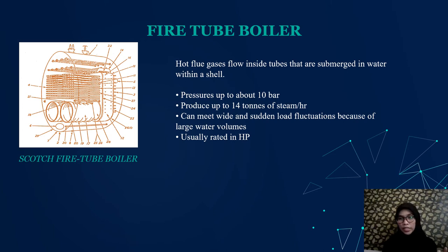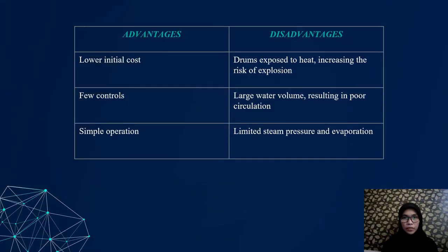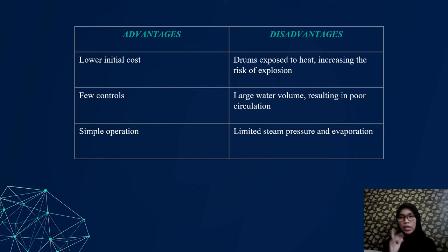This is a fire tube boiler diagram. Fire tube boilers are available in sizes ranging from 500,000 to 75 million BTU input. Advantages include lower installation cost, easy control, and simplified operation. Disadvantages include high risk of explosion, large water volume resulting in poor circulation pressure, and limited steam pressure and vaporization.